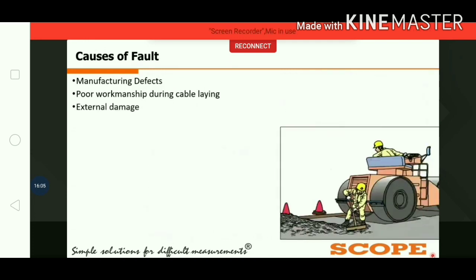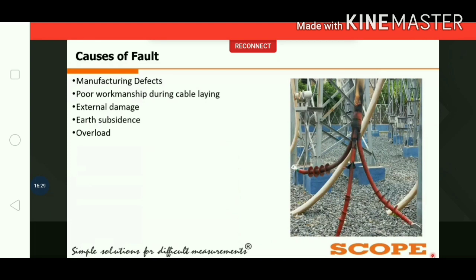The third cause is external damage due to road construction and infrastructure development, which can mechanically damage the cable. The fourth cause is earth subsidence or landsliding, which can also damage the cable. Another cause is overloading: when excess current flows in the cable, the insulation burns at peak stress points such as joints and terminations, as seen in the picture where the cable insulation is burned due to overloading.